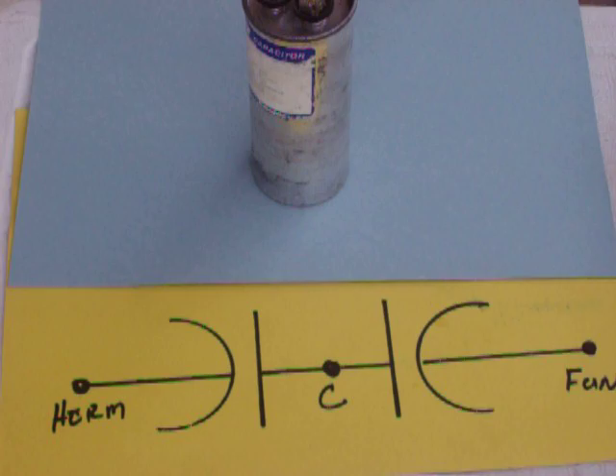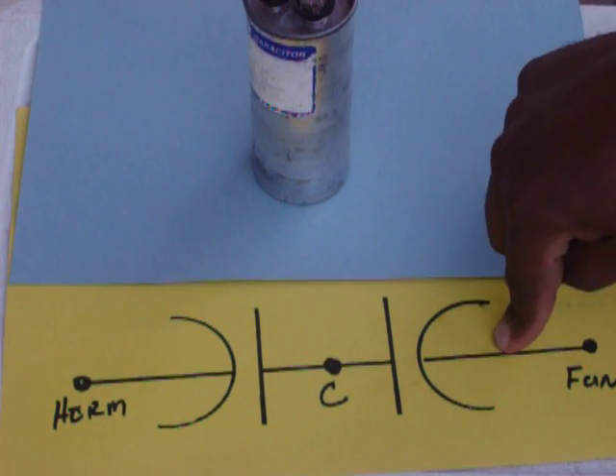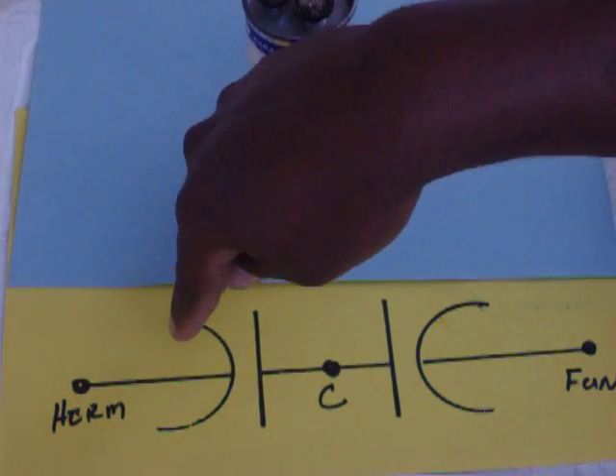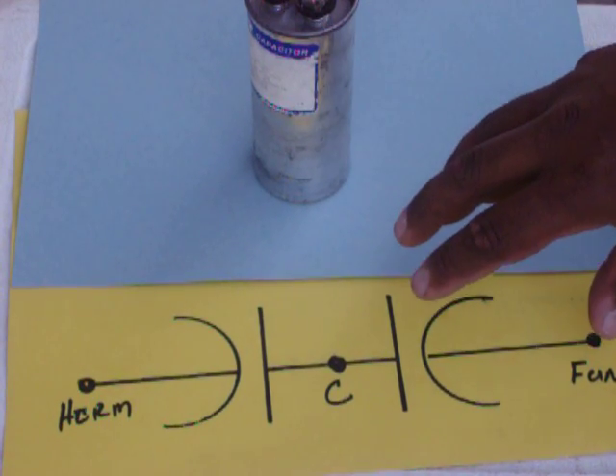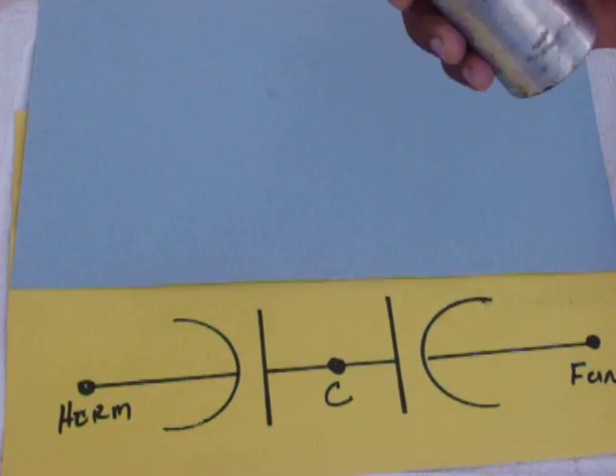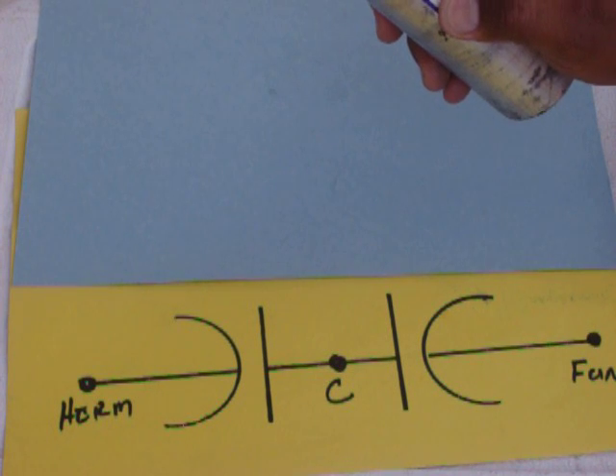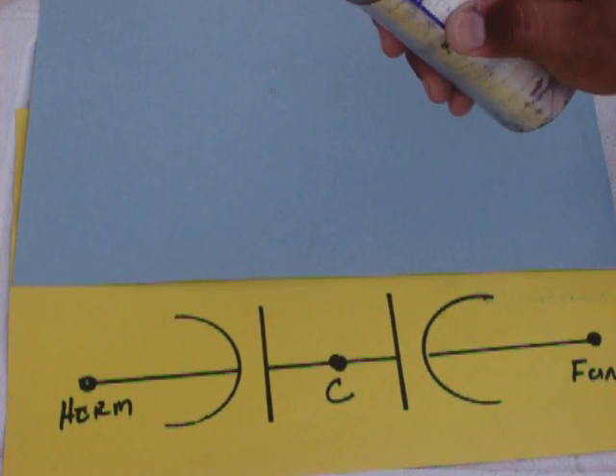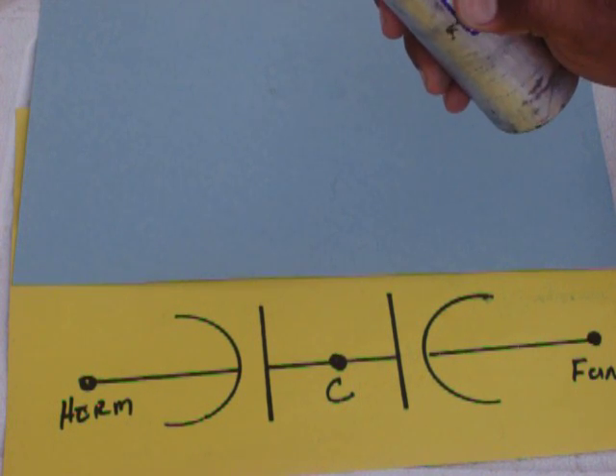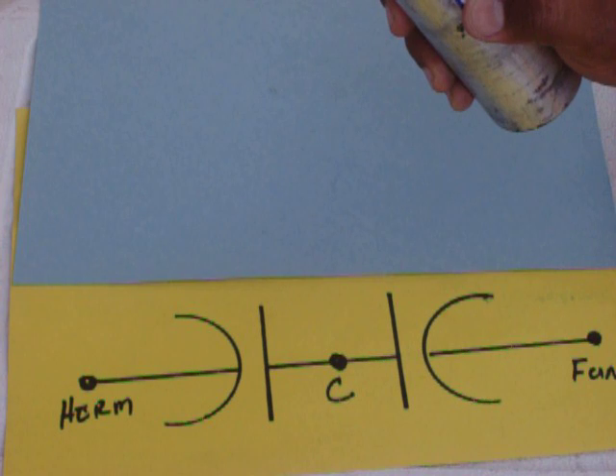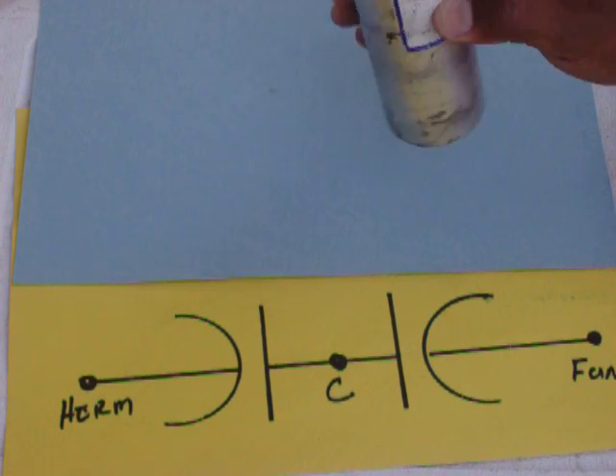So you check that the same. We need to find out what's the microfarads for the fan side, what's the microfarads for the hermetic side. Both are going to have the same voltage reading. So we look at this one. It says 750, 7.5 by 45 by 370. So 7.5 microfarads by 45 microfarads by 370 voltage.